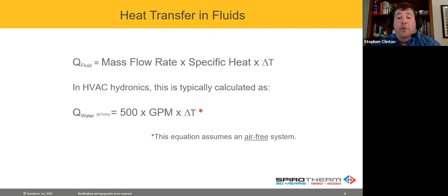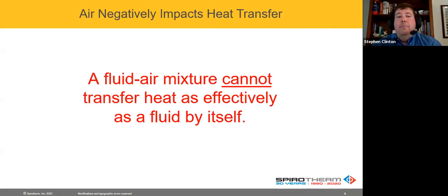It assumes an air-free system. Well, what's the difference? Why is that significant? Because air negatively impacts heat transfer. Air is an insulator. And if you have a fluid-air mixture, basically air mixed in with your fluid, no matter what it is, that fluid cannot transfer heat as effectively as the homogeneous fluid itself, for which the entire system was designed.